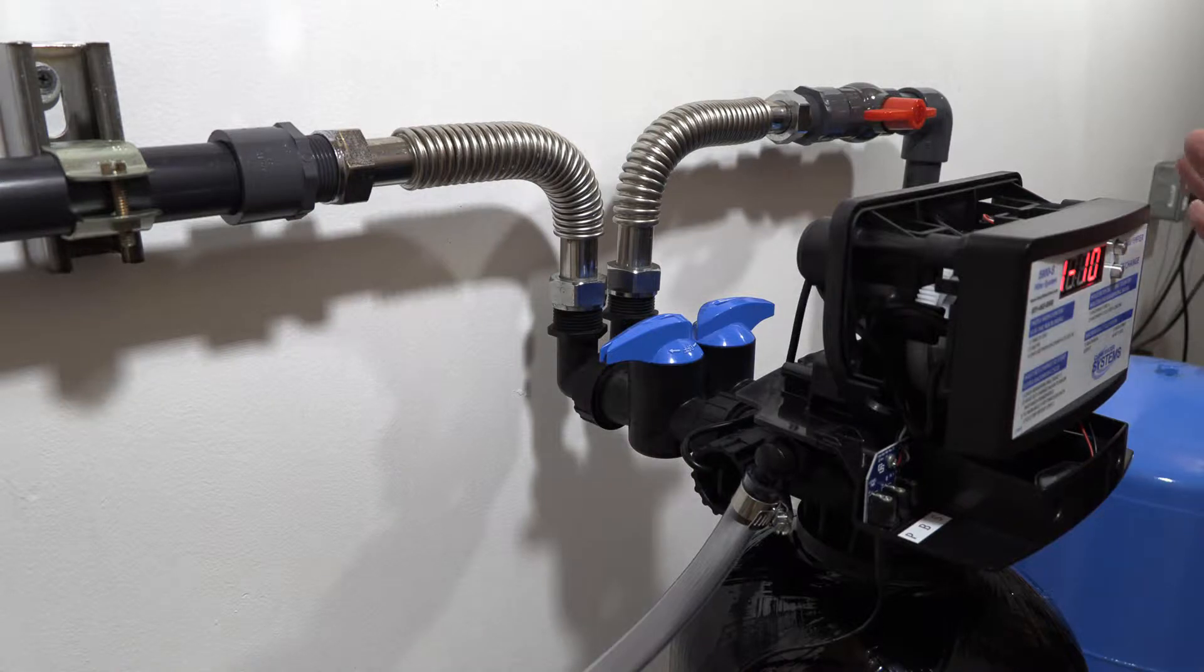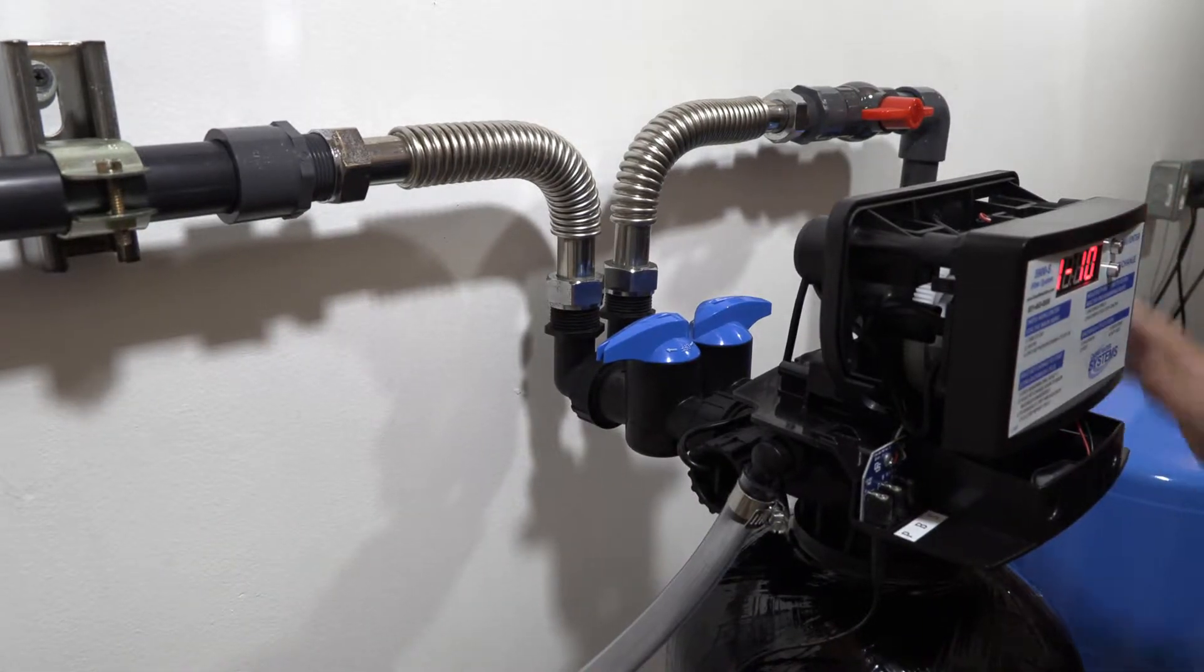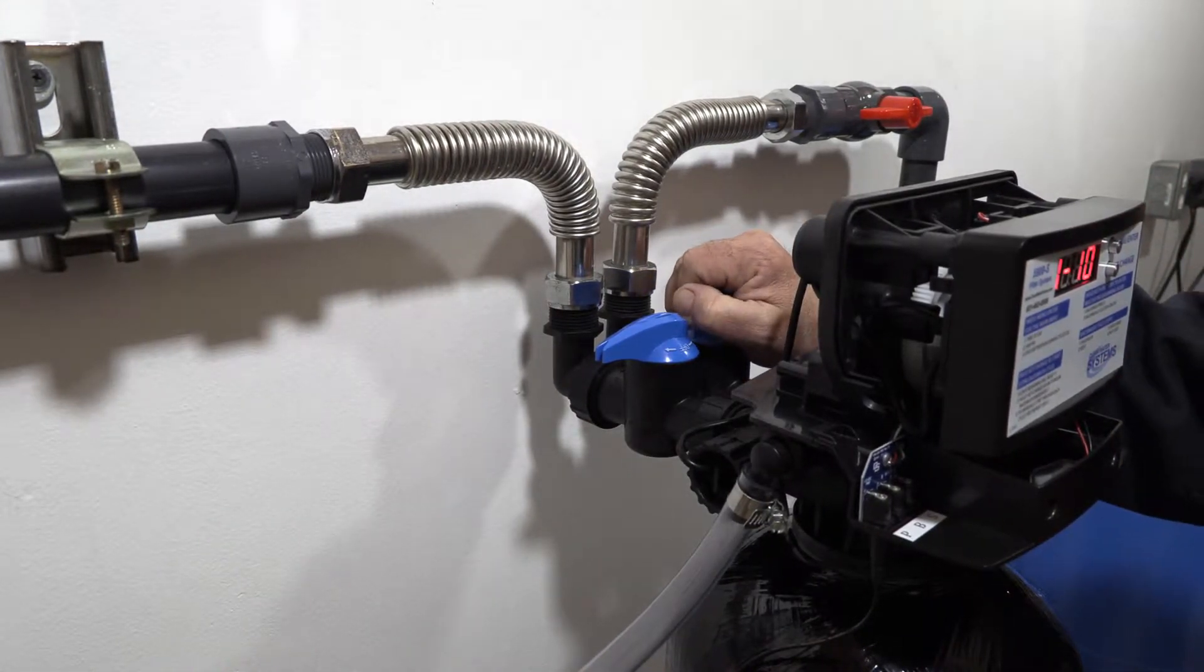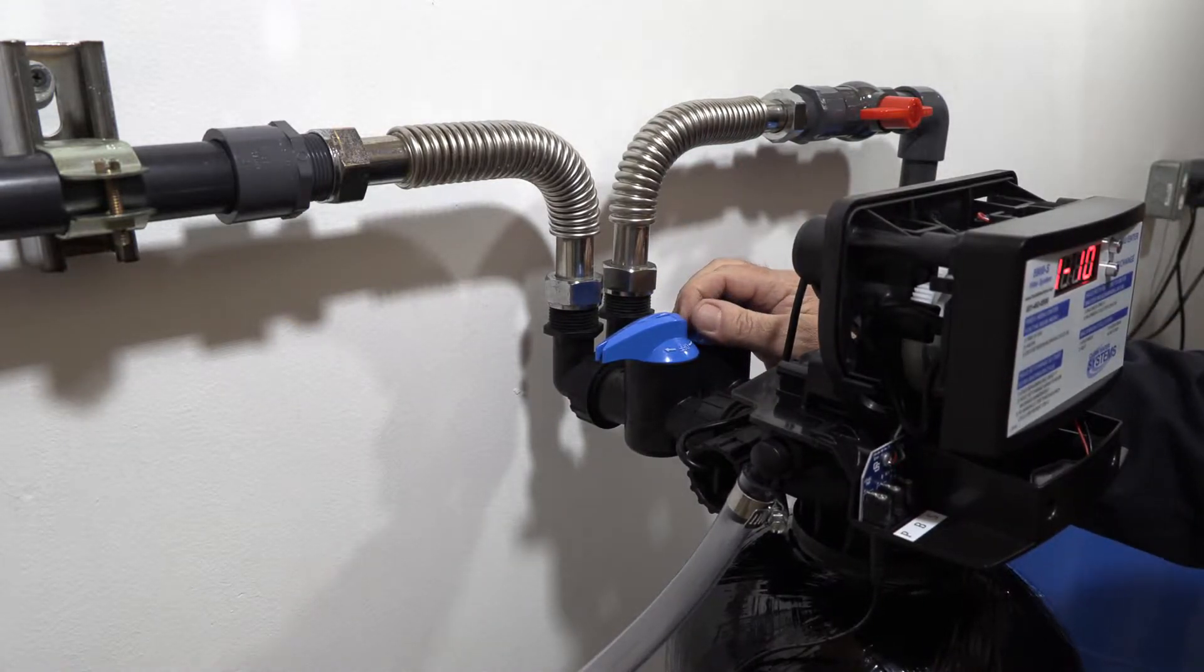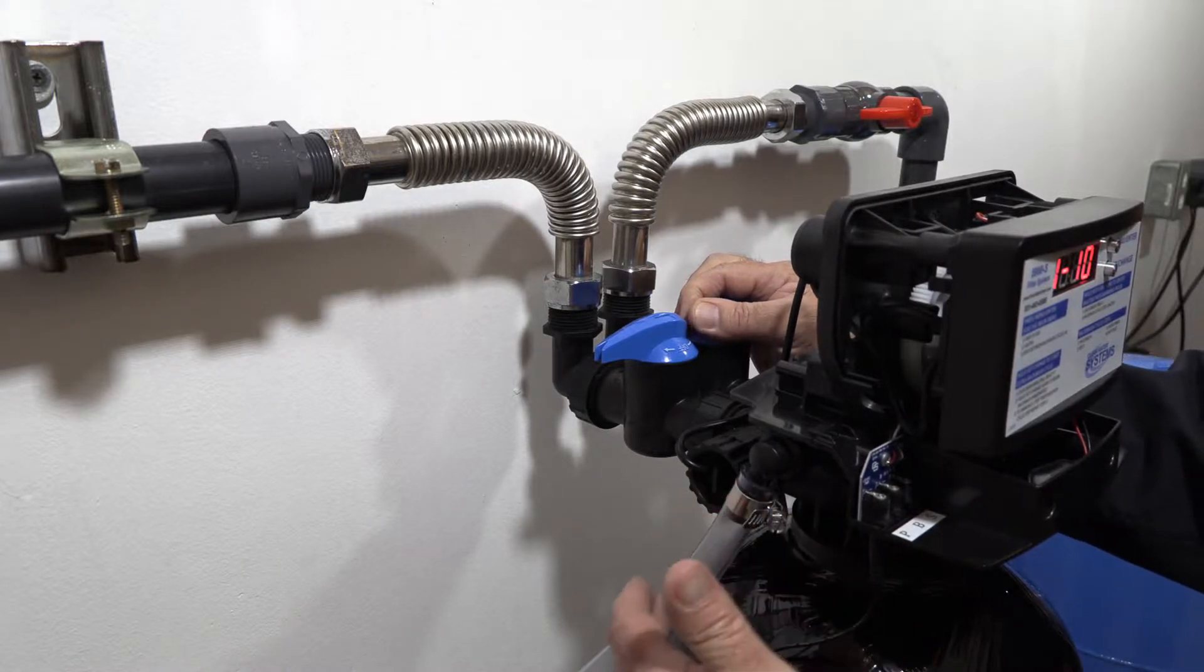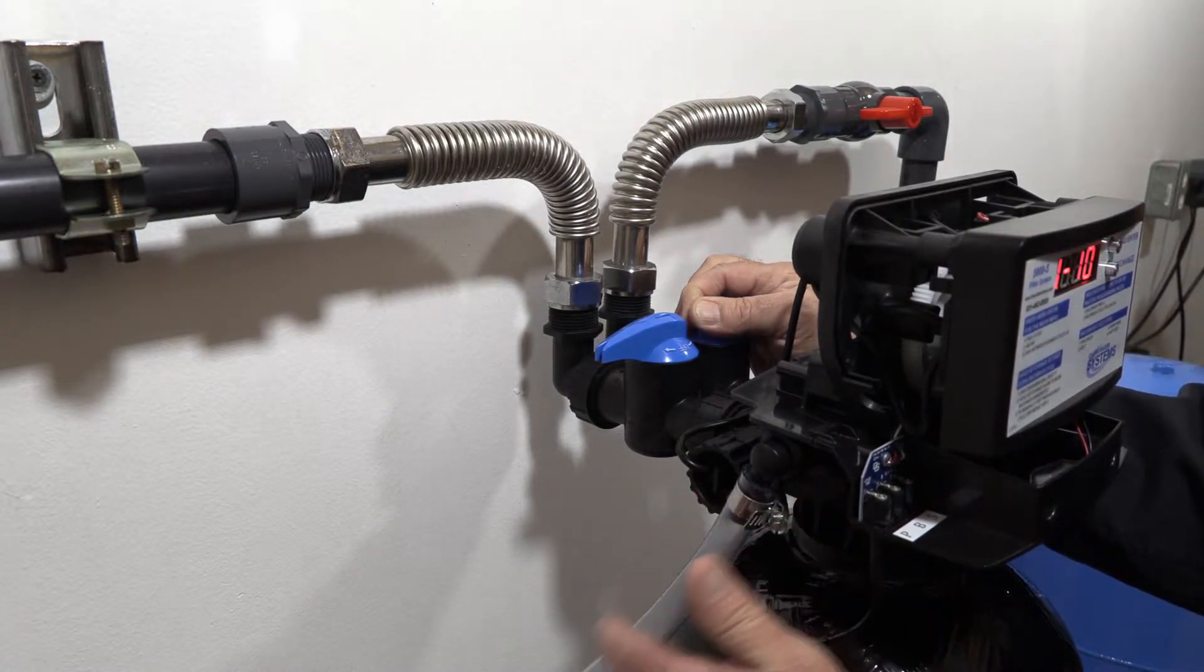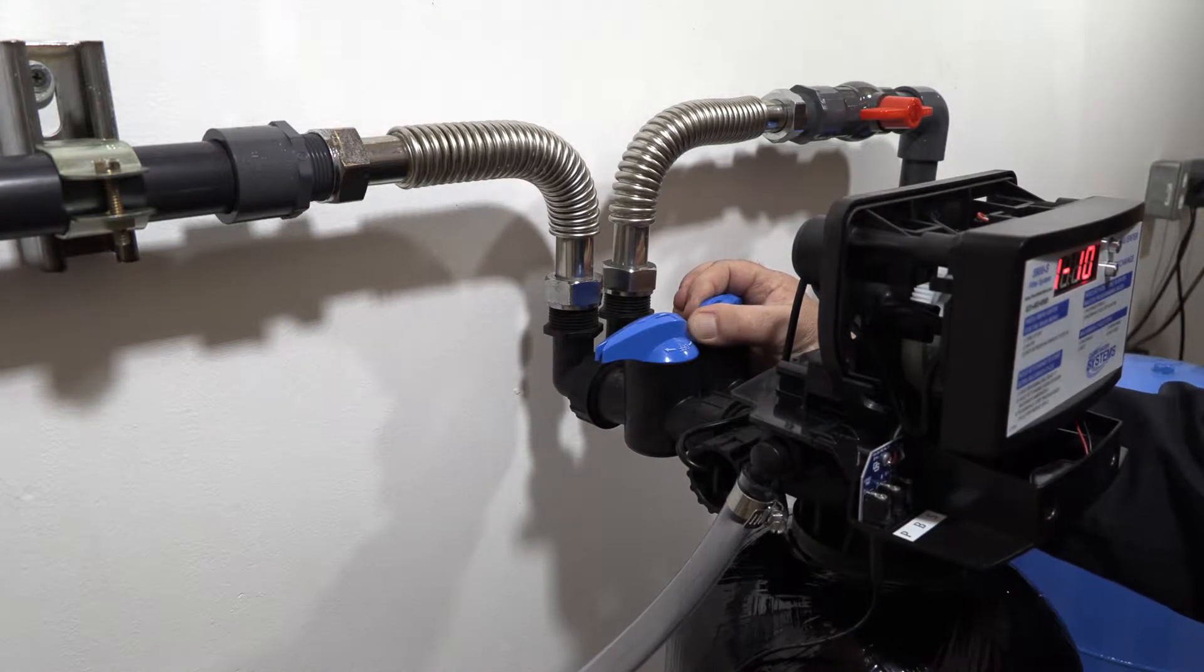So now the valve is in backwash cycle for 10 minutes. What we're going to do is slowly open our inlet bypass valve over a period of about five minutes. What you're going to see initially is air bubbles coming out of here, so just slowly open it.